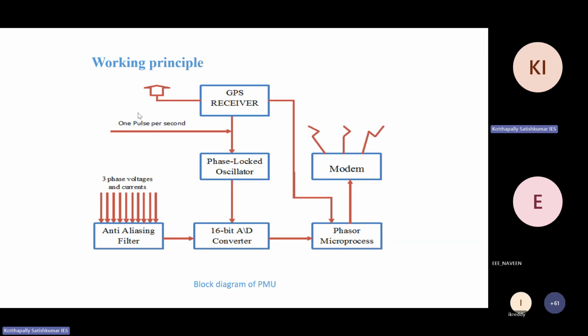The GPS receiver helps to synchronize all PMUs in the power system, and this GPS signal is given to phasor lock oscillators. If the GPS receiver is not available for 1-2 seconds, the phase-locked oscillator will already be in lock with the GPS signal, so it continues locking and there is no impact. Once GPS signal comes back, it continuously links and locks with the phase-locked oscillator, and this gives the converter its signal.